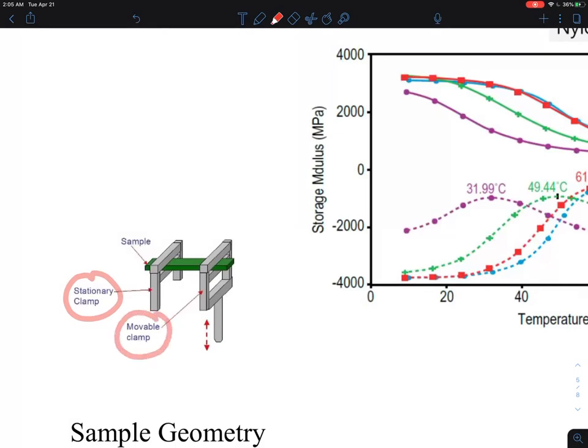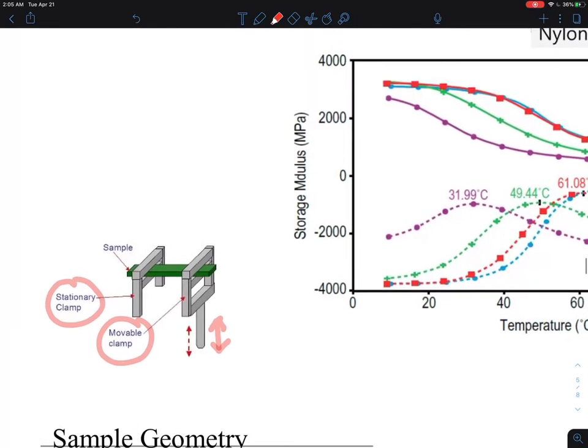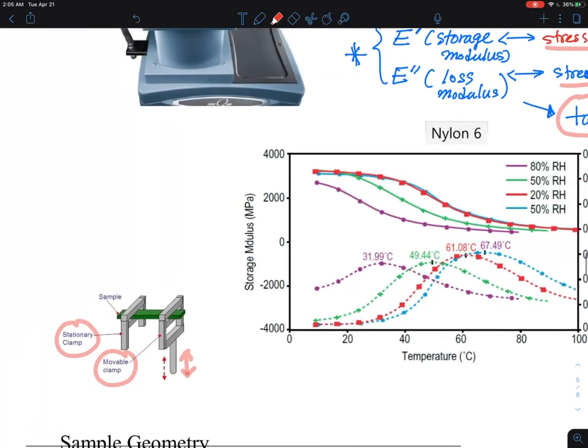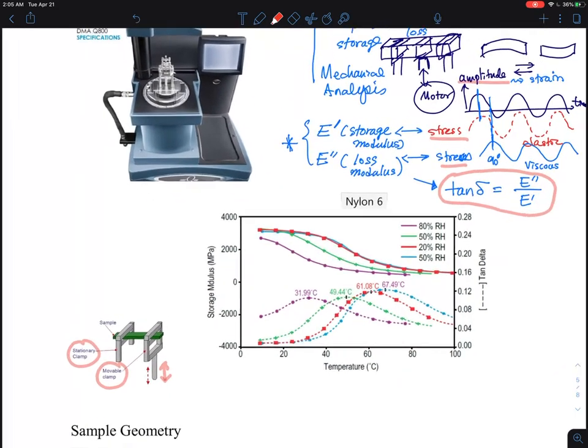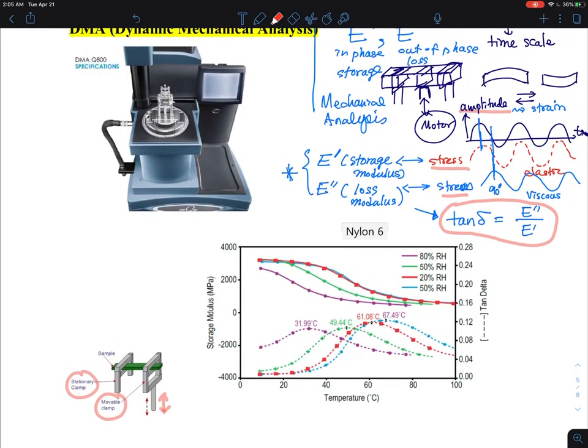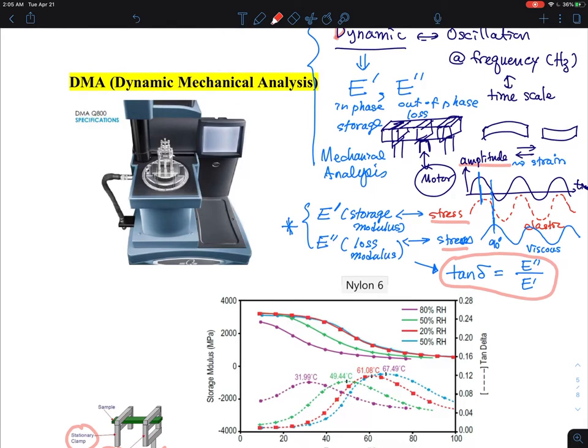Here's an example with a better drawing — this is a single cantilever beam. The green is your sample. This is your stationary clamp and this is the movable clamp that goes up and down. They measure how much bending occurs, giving the in-phase and out-of-phase components. The sample needs to be made into a bar-like shape, requiring a substantially larger amount of sample than DSC or TGA experiments.